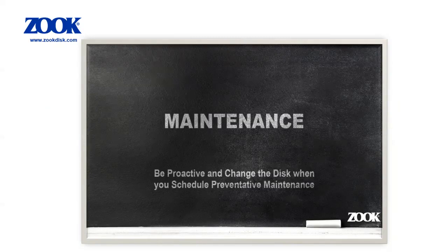We understand how self-serving this sounds, but it is better to have proactive preventative maintenance. The cost of replacing a disk is far less than the cost of an unplanned shutdown and the resulting loss of product and production. There are no specific maintenance tasks that can be performed on a ruptured disk device. If a metal ruptured disk device is taken out of service, then it should be replaced unless it is assembled into a pre-torque holder.